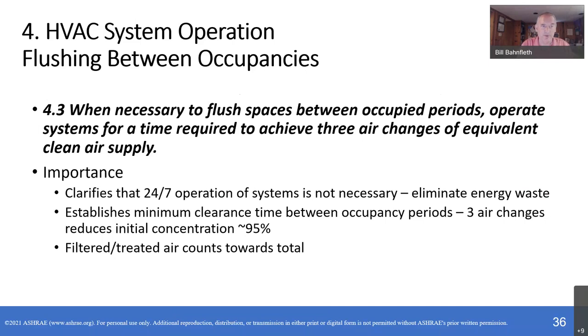It establishes a minimum clearance time. 3 air changes will get us to about 95% clearance in an ideal mixed space situation. You can go farther with more air changes, but this is a good move in that direction. And it also emphasizes that filtered and treated air count towards the total. So you may only have 2 air changes of outdoor air, which means it takes an hour and a half to do 3 air changes. But if there's good filtration and high recirculation rate through the filters, it could be 20, 30 minutes.